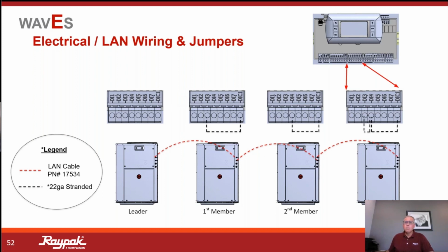Okay, good. Any other questions? I got one, Paul. Yeah, Aaron. Hey, Paul, I got Eric Connor with me. We actually have the factory supplied cable that could be ordered to do that jumper sequence. Okay, let me feed back what I heard. Are you talking about the LAN cable? Yes. Okay, so you're right. It is communicating sequentially unit to unit to unit. That is one wire in daisy chain sequencing that communicates all of these. That's absolutely true. But we still need to have the unit have a unit identifier of where it is in the sequence. So you're absolutely right. This is a part number that is an optional cable available when you order the unit. Highly recommend them being utilized.